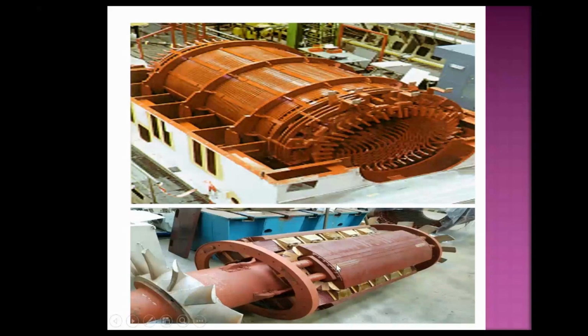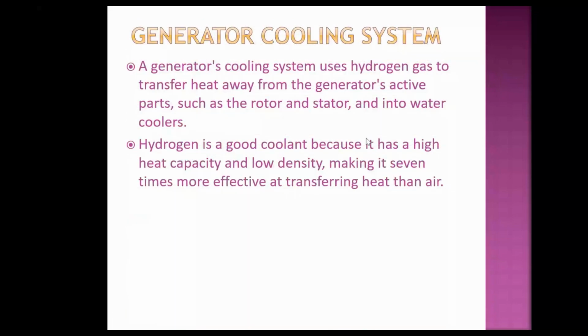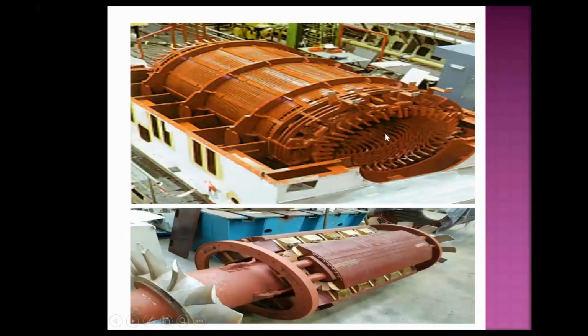The generator principle is not our concept here. When the shaft is rotating inside the stator, a huge amount of heat is generated inside the generator. That heat has to be removed from the generator. Here, the main purpose of hydrogen is cooling the core. This is the core. So for cooling the core, we use hydrogen.